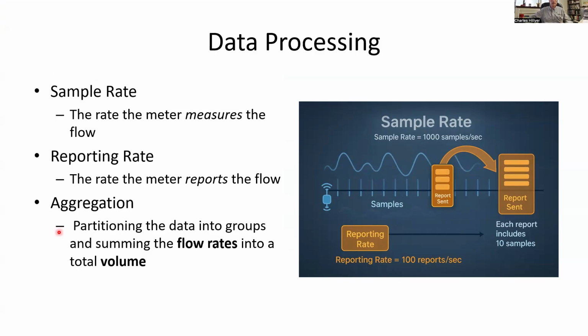So the data that you actually see is based on the reporting rate. Many types of meters will take lots and lots of measurements and average them together. That improves the accuracy of the data that gets reported to you. It also improves the stability of the data that gets measured. Some of these measurement technologies have quite a bit of noise, but you can get rid of that noise by taking a lot of measurements and averaging them out. And that's what's being reported to you. So if you're getting data that's reported to you once an hour, your meter may actually be sampling at a much higher rate than that.